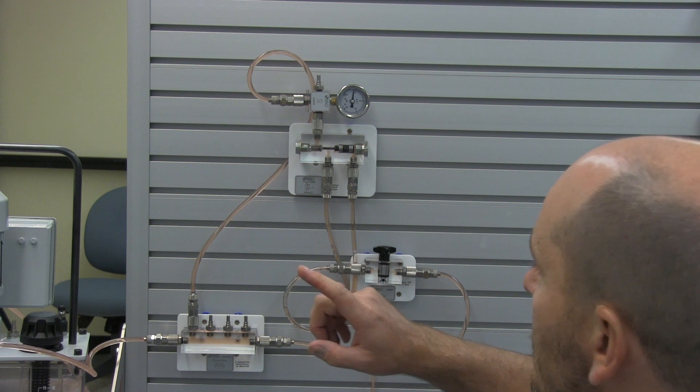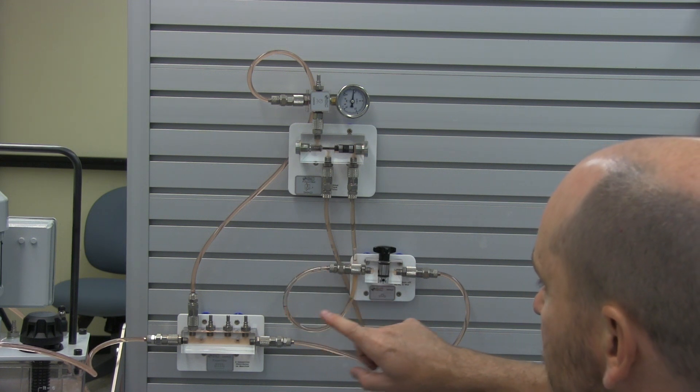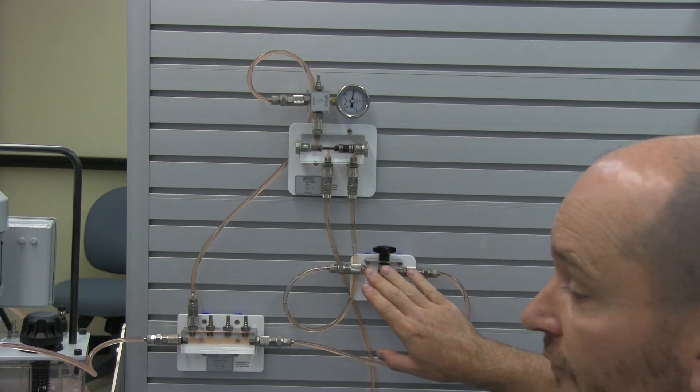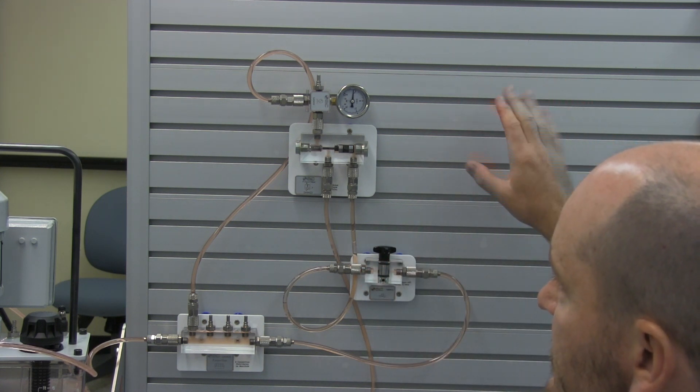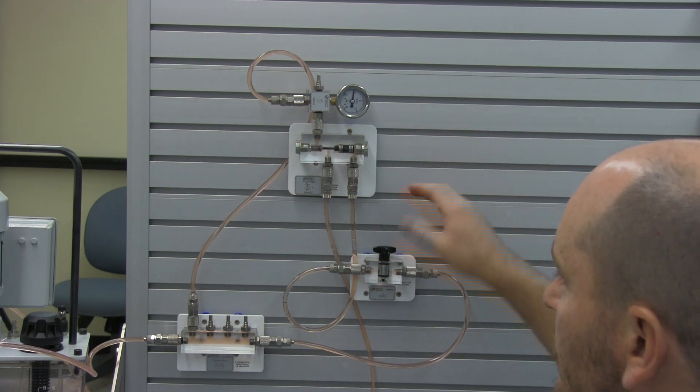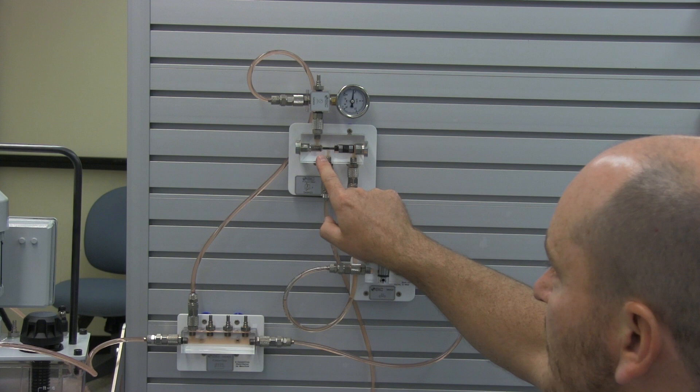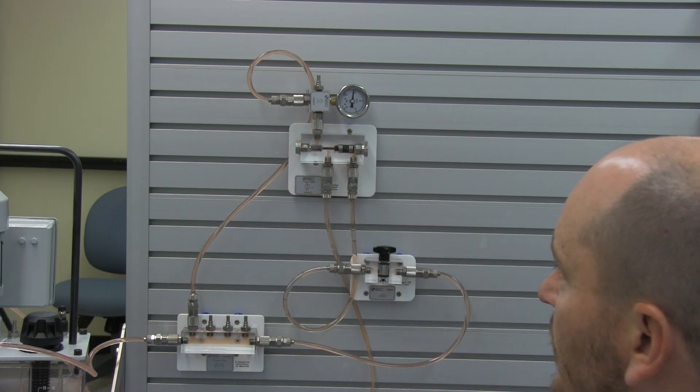Usually what you will see is this signal coming from a pilot signal teed off somewhere else in the system, letting you know you have enough pressure. But in this case I'm just demonstrating that by sending this signal here, where there's no flow, it's just pressure opening this up, allowing flow to go down this way.